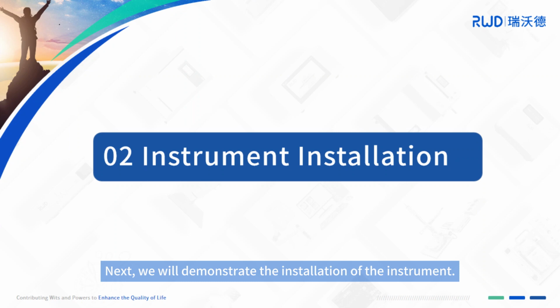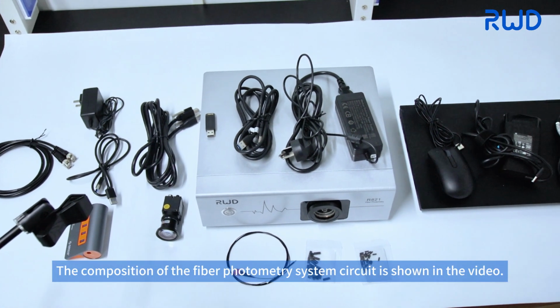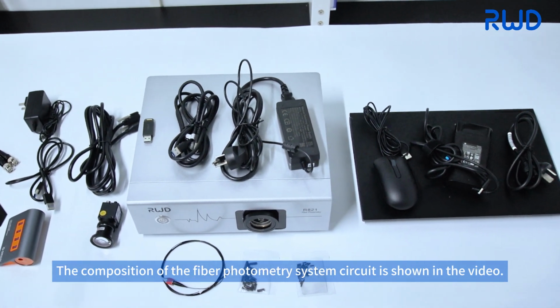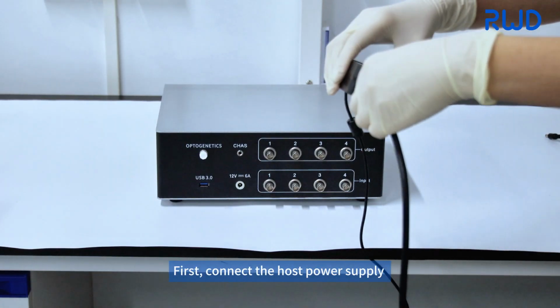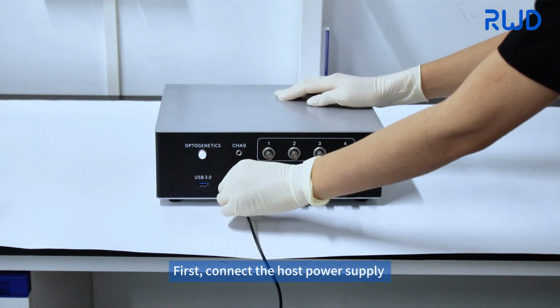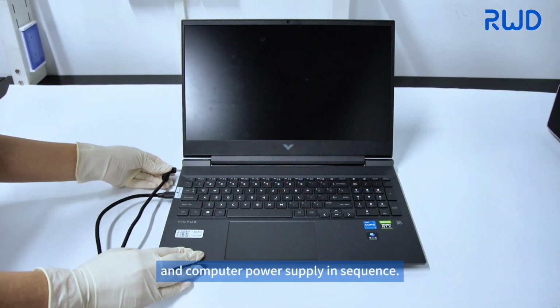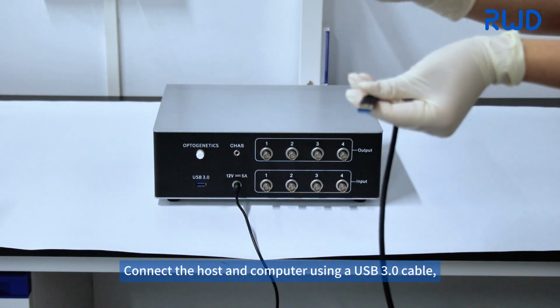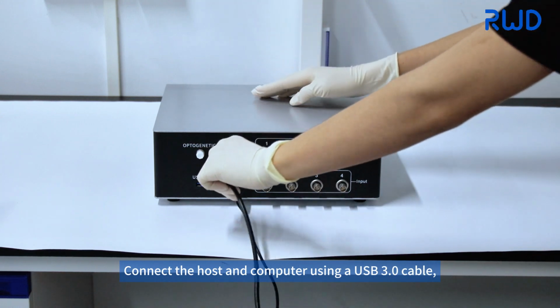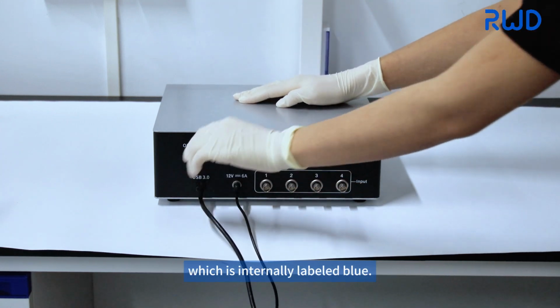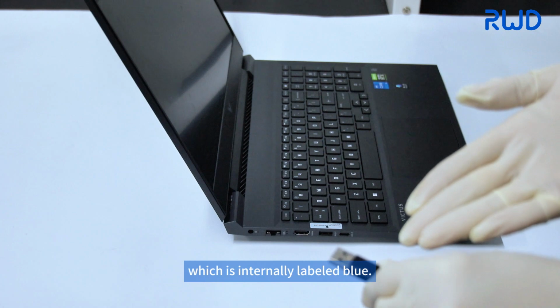Next, we will demonstrate the installation of the instrument. The composition of the fiber photometry system circuit is shown in the video. First, connect the host power supply and computer power supply in sequence. Connect the host and computer using a USB 3.0 cable, which is internally labeled blue.